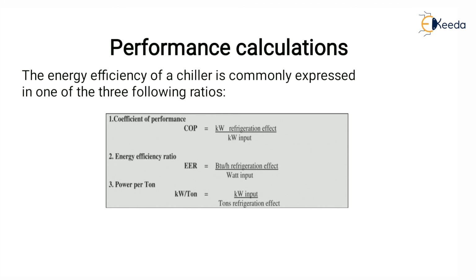Next is performance calculation. Energy efficiency of chiller is commonly expressed in one of the three following ratios. Either it can be coefficient of performance, COP equals kW refrigeration effect divided by kW input, or energy efficiency ratio, EER equals BTU per hour refrigeration effect upon watt input, or the third, power per ton, kW per ton equals kW input upon tons refrigeration effect. So we can get the energy efficiency of the chiller from this.